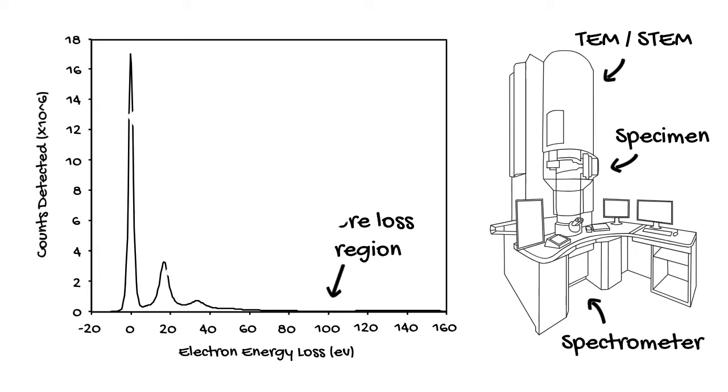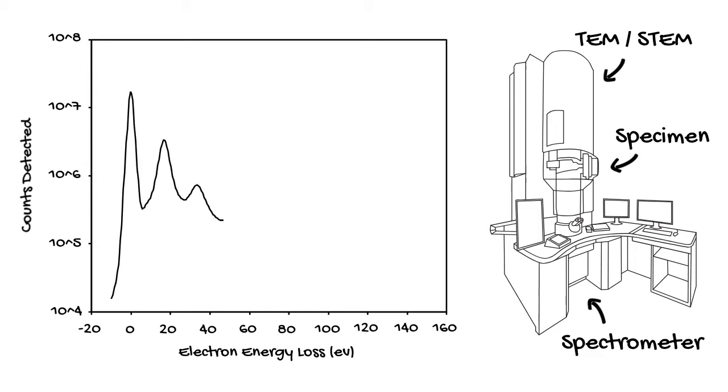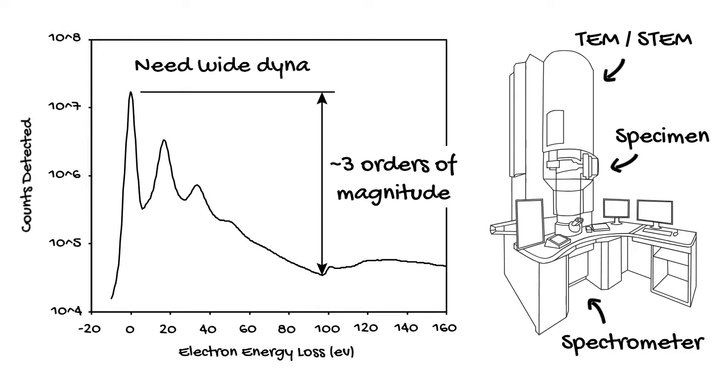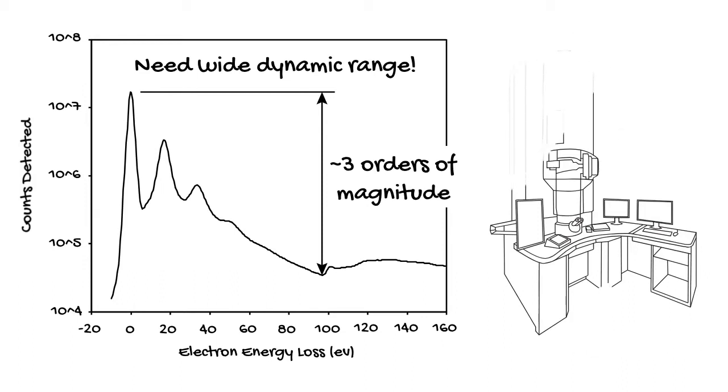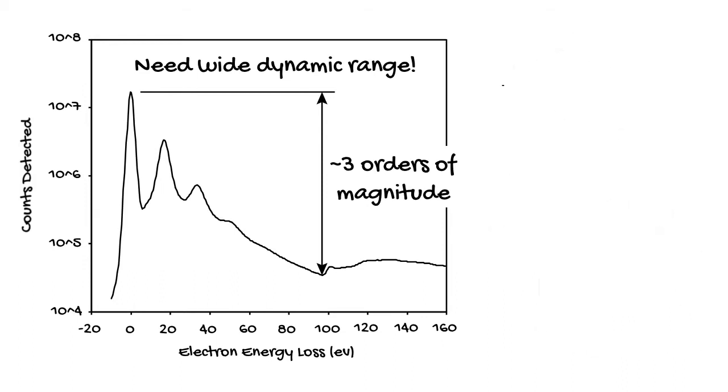Capturing this data turns out to be quite challenging, though, due to the wide range of intensities in the EELS spectrum. If we replot the EELS spectrum on a log scale, the issue becomes obvious. The intensity of the EELS spectrum often spans three orders of magnitude or more. An effective EELS detector must therefore have a wide dynamic range, so that it can capture the very intense zero loss peak, the intermediate low loss region, and the very weak core loss region.